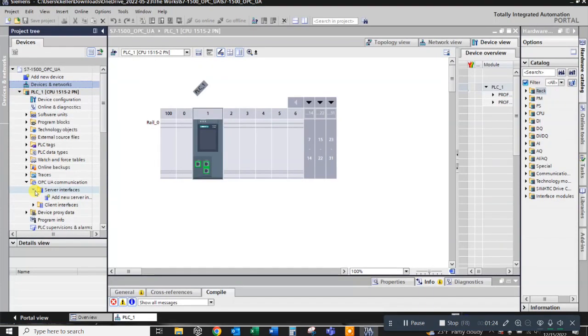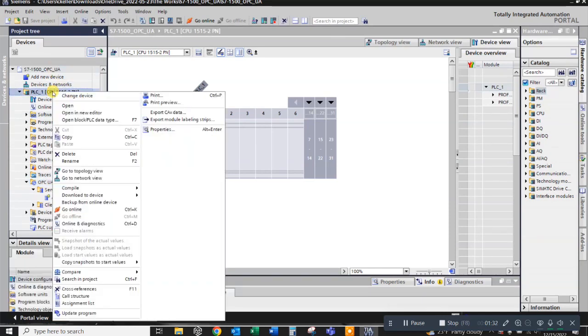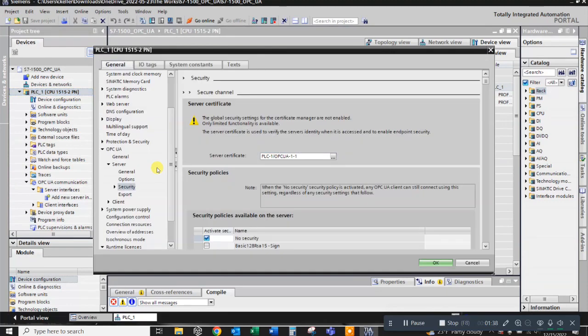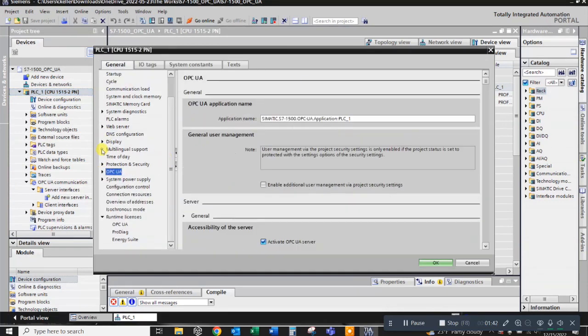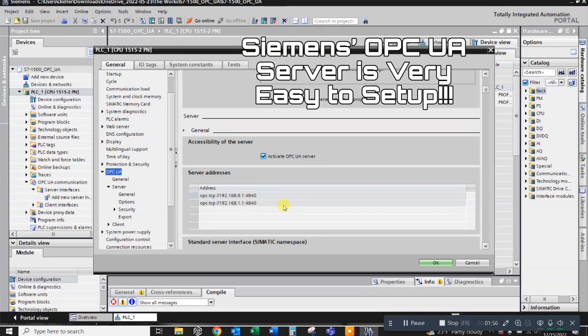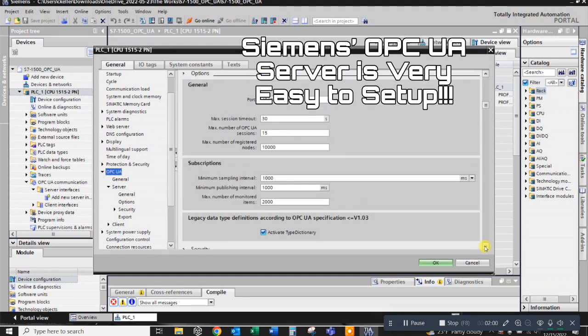I'm going to right click on the PLC, go to Properties, and then I'll go down to the OPC UA tab. Then I'm just going to check a couple boxes. I'm going to pretty much open this thing wide open.